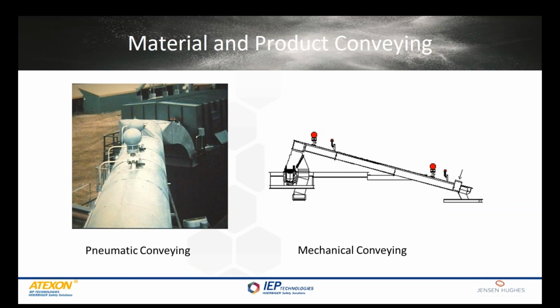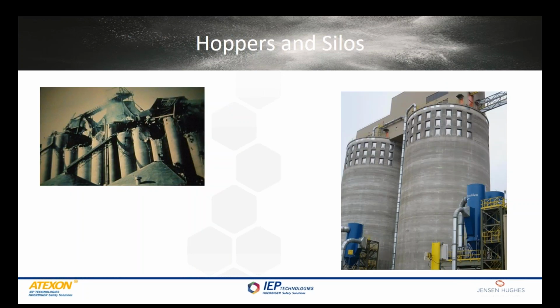Mechanical and pneumatic conveying are both explosion threats within biomass facilities. Hoppers and silos: Mika discussed earlier the potential for spontaneous ignition. You also can have hot burning material that's being transmitted from somewhere upstream that can get into hoppers and silos. The photo on the right is actually a biomass facility that was converted from a coal-fired plant to biomass, and as you can see, those particular silos are equipped with explosion vents. Those vents have to be placed above whatever the upper product level is within the protected vessel, since vents aren't made to have product resting against them.